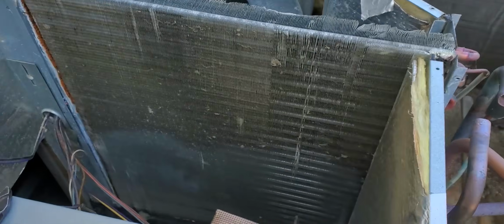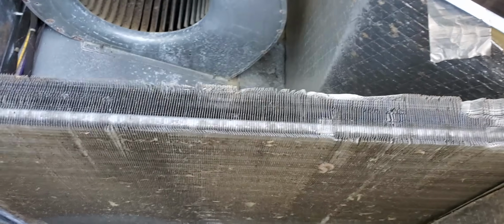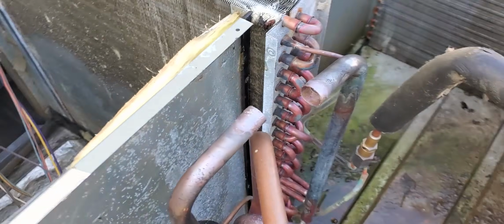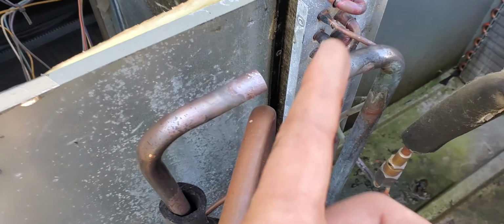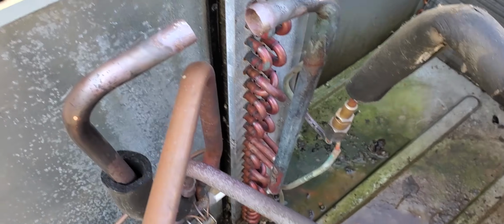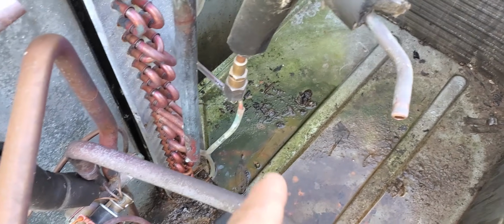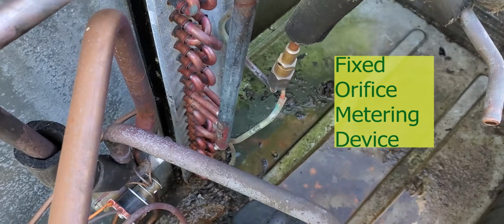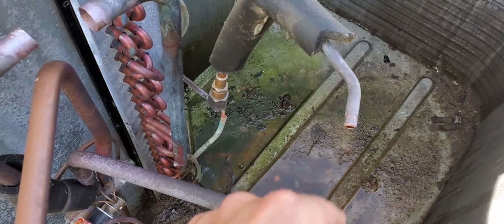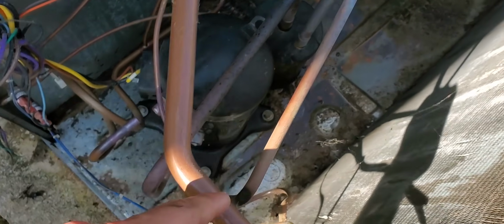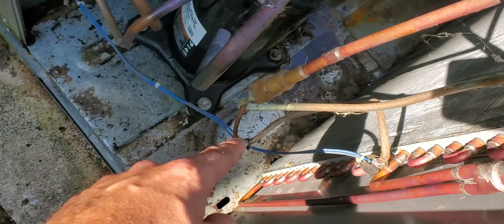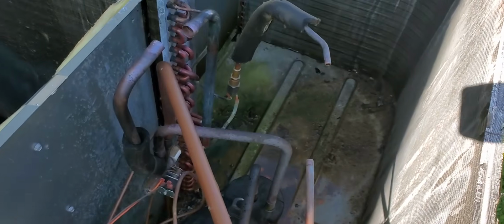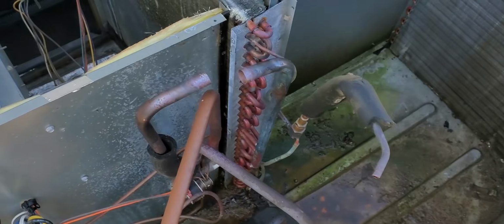And this is the indoor coil that was leaking. Little thin indoor coil, evaporator coil. And I just used my torches. I've got that connection loose, and then this connection right here is the metering device for the evaporator. I'm going to put a filter dryer between here and here in the liquid line, and this is the metering device for the condenser section, condenser and evaporator.